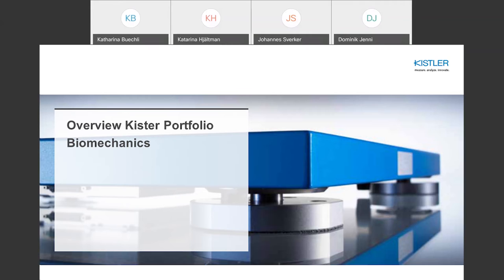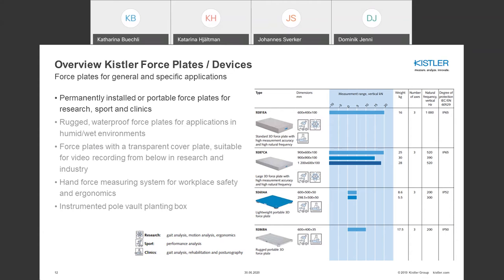Kistler has different force plates for permanent installations and different portable force plates. Main applications are within research, sport, and clinics. Products are listed in a downloadable brochure from the Kistler website. The main products are available in different sizes with different measurement ranges. The portable plates have a lower measurement range not due to sensor technology, but because they're made as light and portable as possible, though they still have a quite high natural frequency.